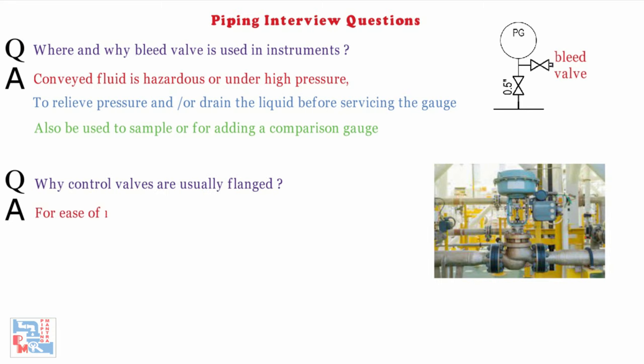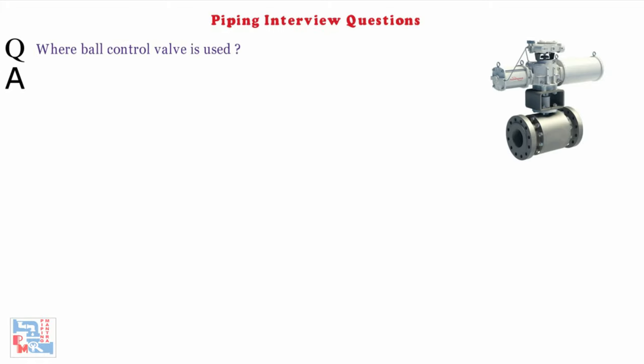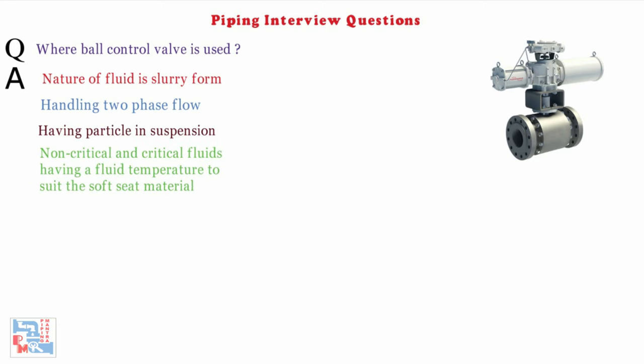Next: why are control valves usually flanged? Control valves are usually flanged for the ease of installation and removal during maintenance. Next: where are ball control valves used? Ball control valves are suitable where the nature of fluid is slurry form, or handling two-phase flow having particles in suspension.